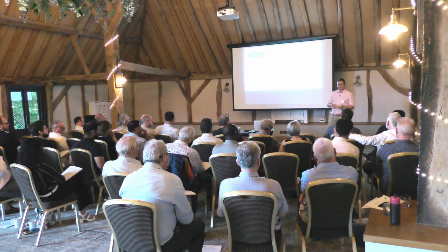And therefore, by creating an open plan on the ground floor with a staircase terminating into a lounge or a kitchen, you are making the situation worse, and therefore you would expect compliance to ADB, which would be the provision of FD20 doors, fire-resistant enclosures, etc. Now again, you can vary from the guidance in ADB, but the tendency is towards liability of non-compliance.